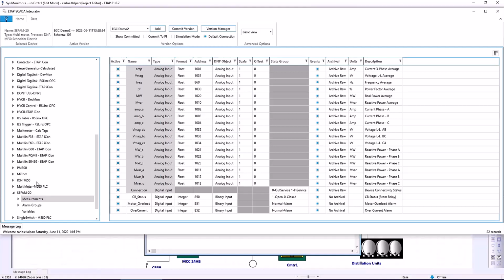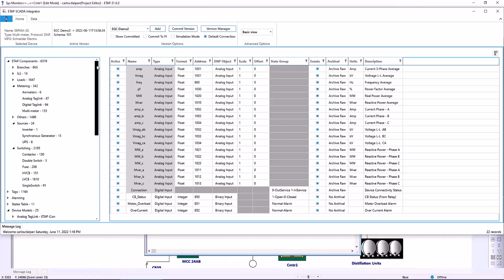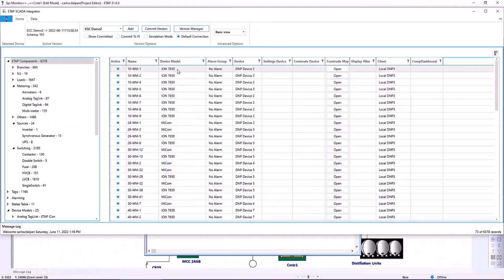Each device model is linked to all the components in the electrical model using the same characteristics. Once an ETAP component is linked to a device model, the SCADA Integrator will dynamically create tags. This workflow makes the process of integration very simple and fast, because every component is linked to a live measurement already modeled on the digital twin.